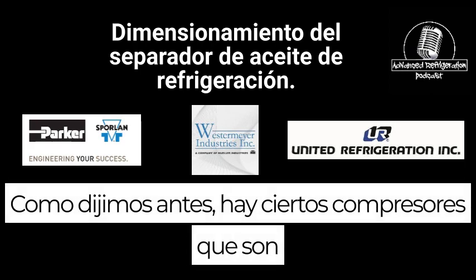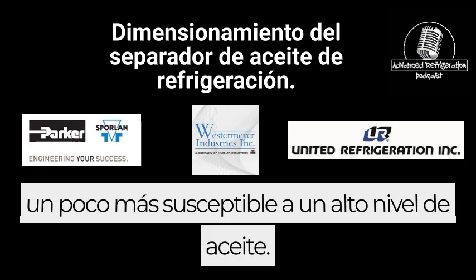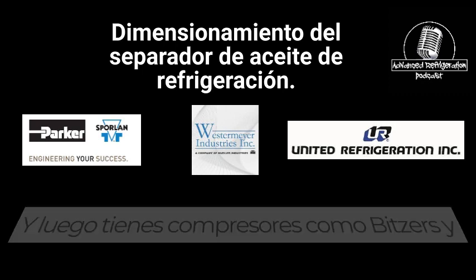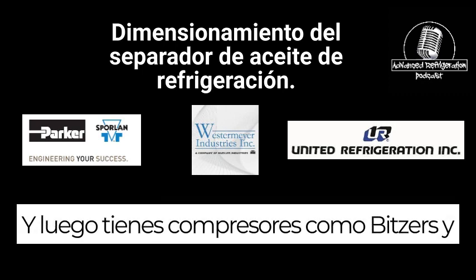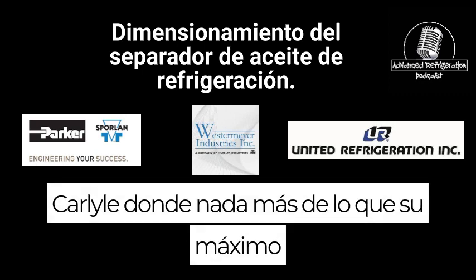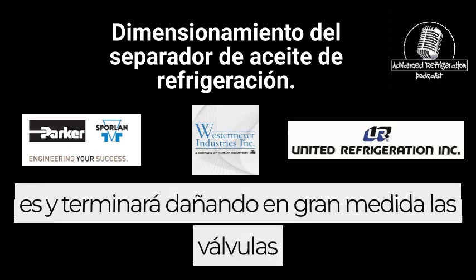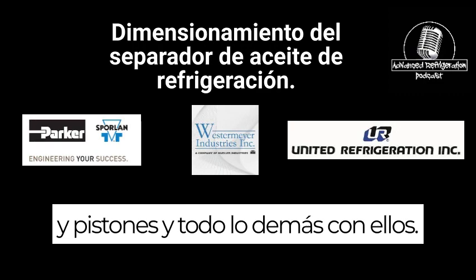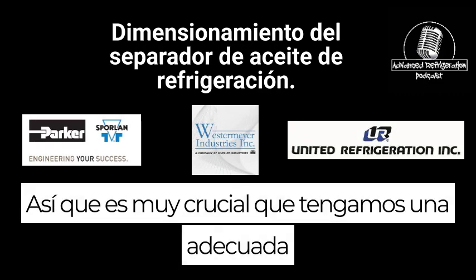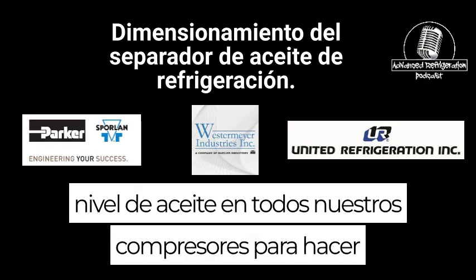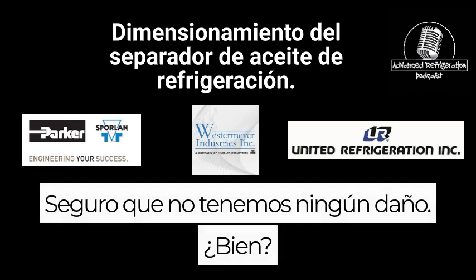Like we said before, there are certain compressors that are a little bit more susceptible to a high oil level. And then you have compressors like Bitzers and Carlyle where anything more than their max, and you'll end up majorly damaging valves and pistons and everything else. So it's very crucial that we have a proper oil level in all of our compressors to make sure that we don't have any damage.